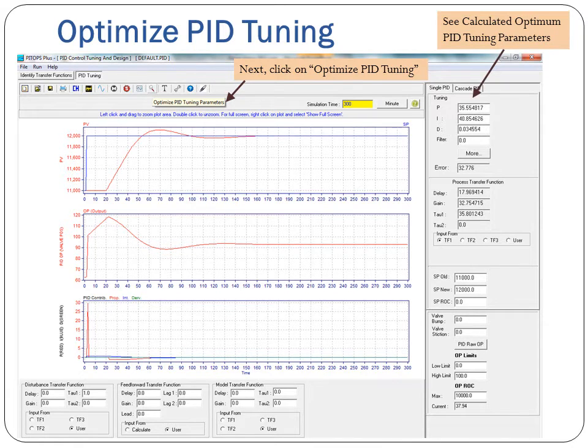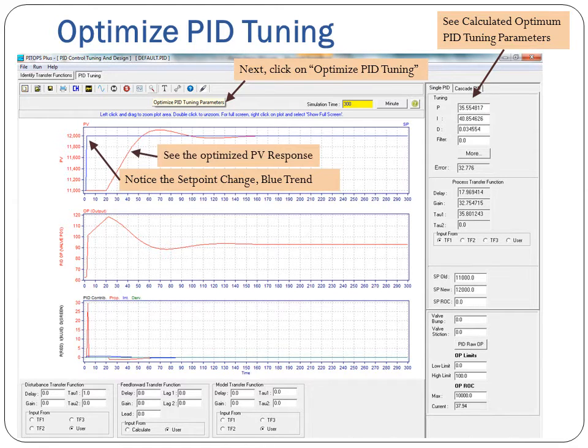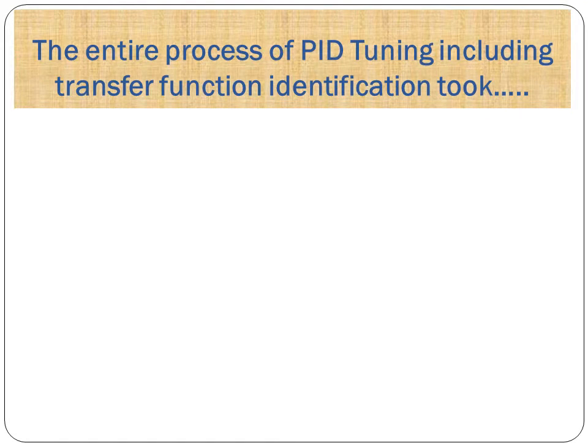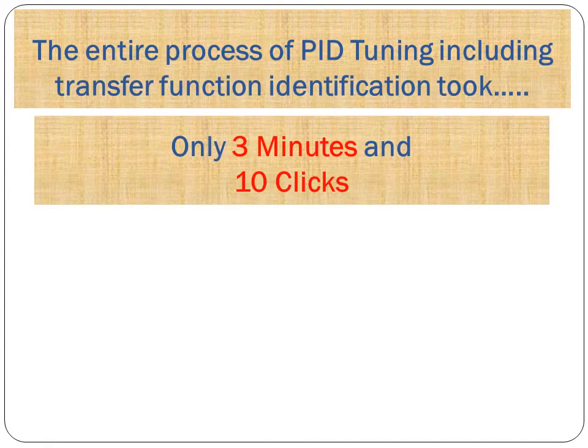See the calculated optimum PID tuning parameters. Notice the setpoint change blue trend and see the optimized PV response. Examine the AC PID OP output trajectory. The entire process of PID tuning, including transfer function identification, took only 3 minutes and 10 clicks.